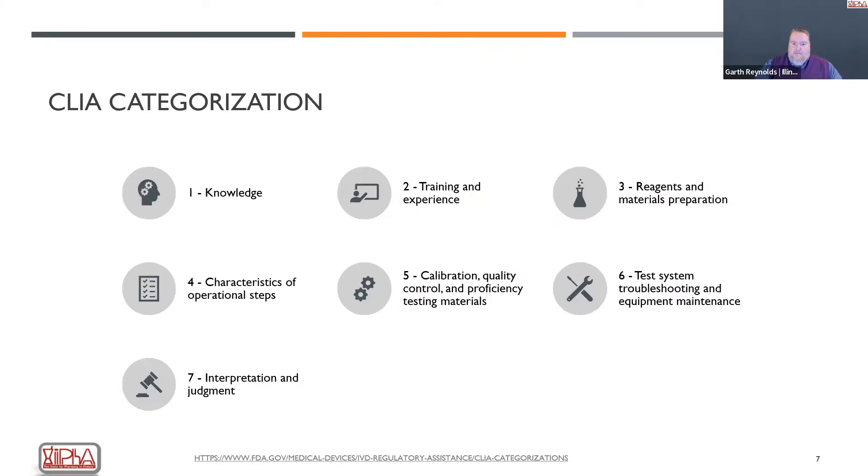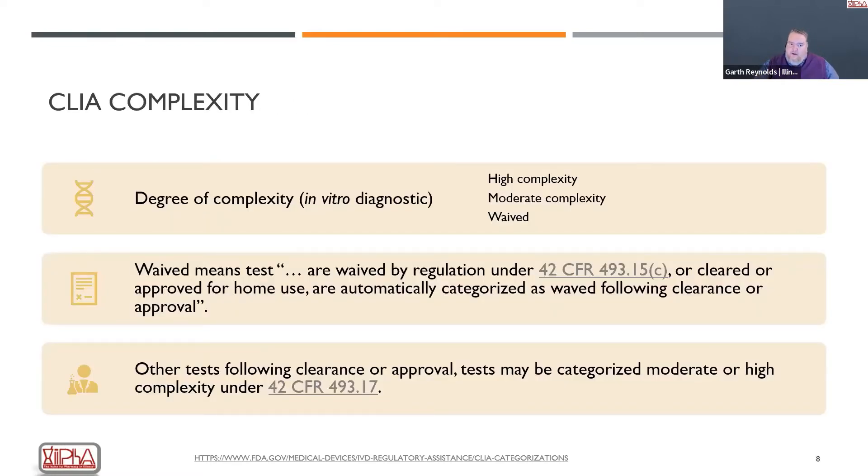The categorization of laboratory tests is very complex. There are seven different categories the FDA considers when determining a test's complexity: knowledge, training and expertise needed; reagents and materials for preparation; characteristics of the operational steps; how hard it is to calibrate quality control; proficiency of testing materials; troubleshooting and equipment; and how easy or difficult the interpretation and judgment is. This is all done on a scoring system. Complexities fall into three categories: high complexity, moderate complexity — where the majority of tests lie — and waived tests.